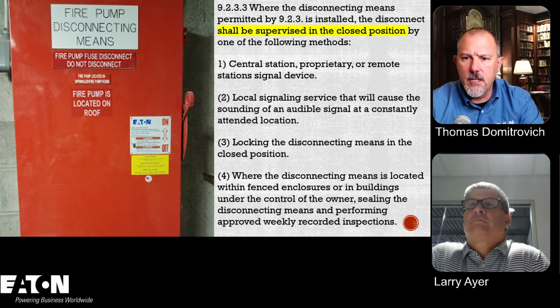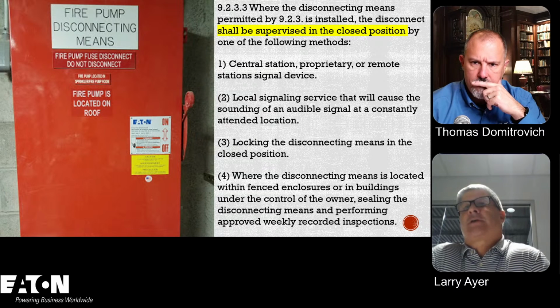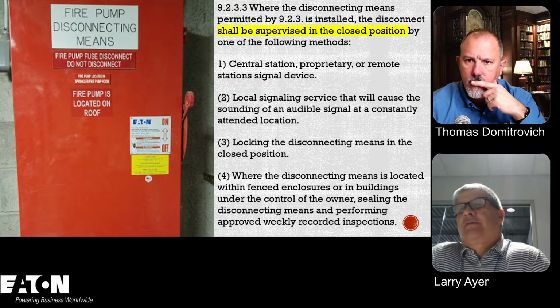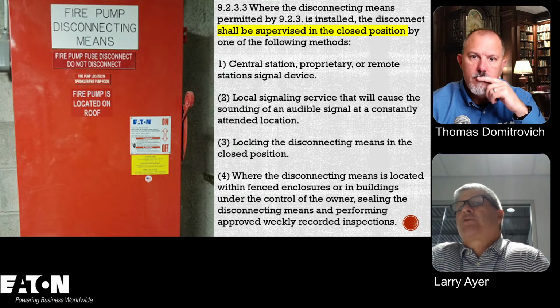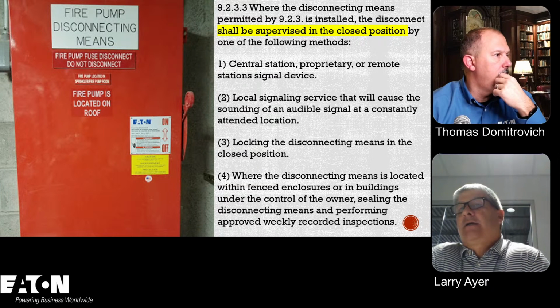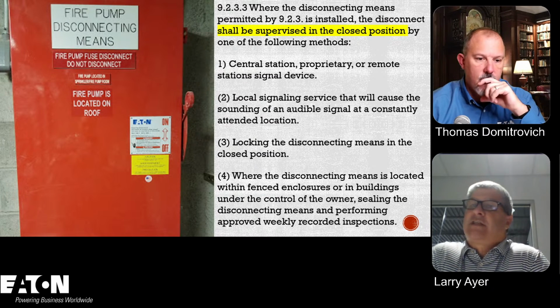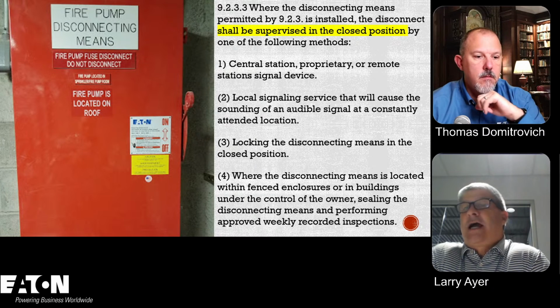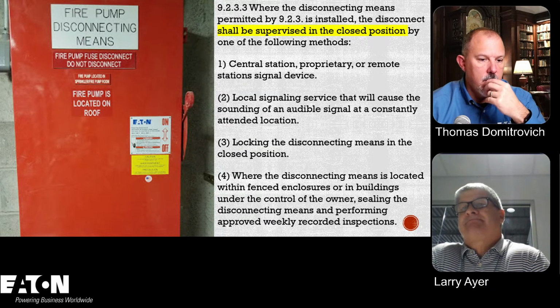Did we cover this one already? Locking disconnect means in the closed position. We already talked about that. Supervised in the closed position. Right. So you've got to supervise it. You want to make sure that if you open this up, it sends a signal in some fashion to the fire alarm that you opened it up and turned that power off. So you can either supervise that by a connection to the central station, or you can actually lock the disconnect means in the closed position. You can do that as well. I've seen it in both cases. I actually think people do both 1 and 3.